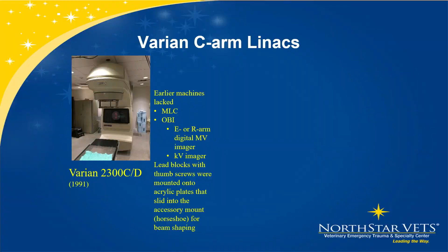If you can imagine, every time that linear accelerator turns, it's a new field shape because tumors aren't a sphere in 3D. So we had to run in, take that sheet out, move all the lead blocks, thumb screw them back in, put that back in, go out, image, and then treat. Luckily, we have the multi-leaf collimator. We don't have to do that anymore. The other thing that has been a real big help is some kind of onboard imaging.